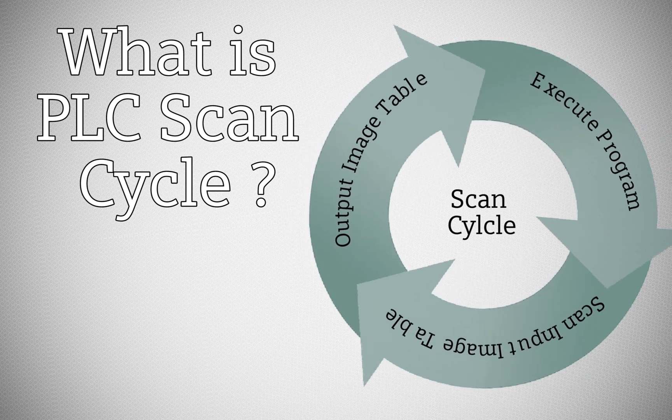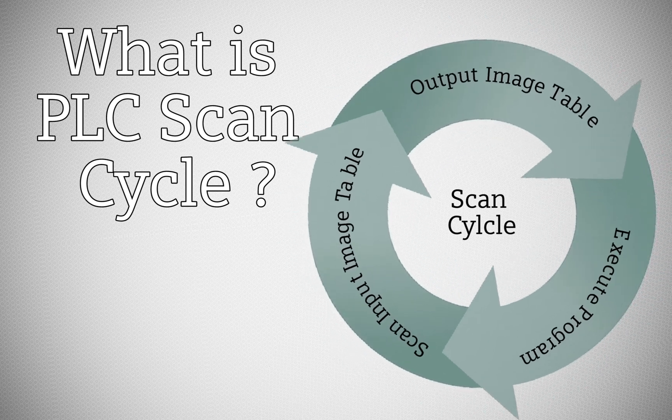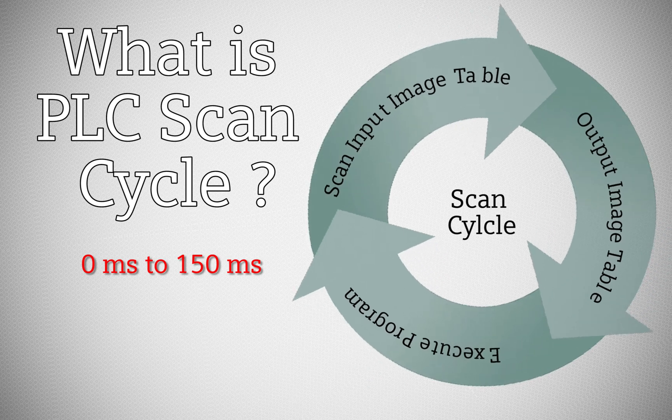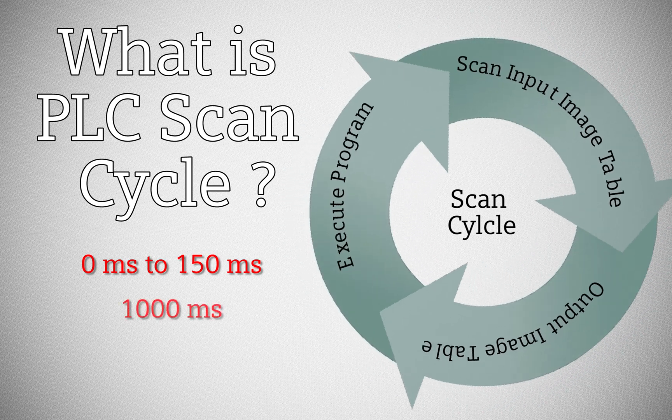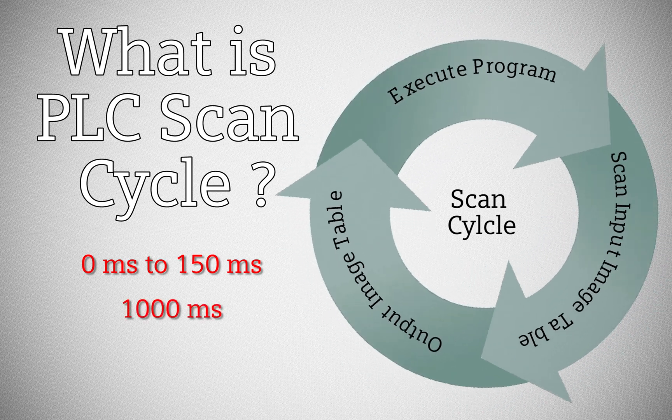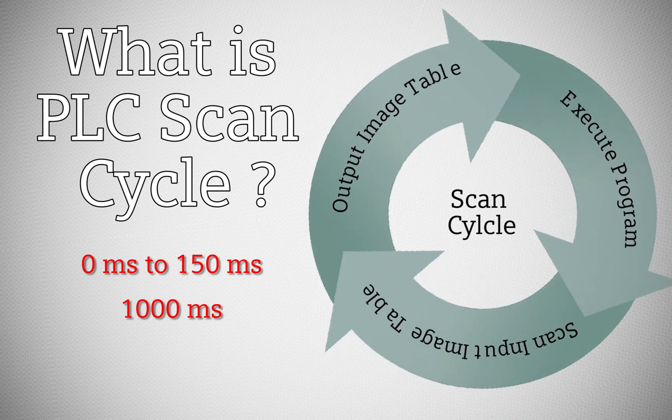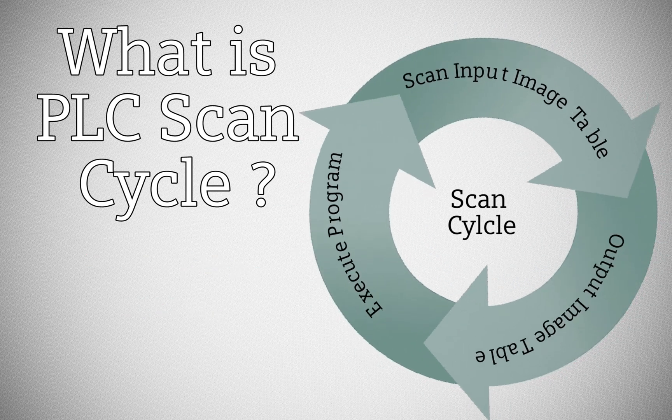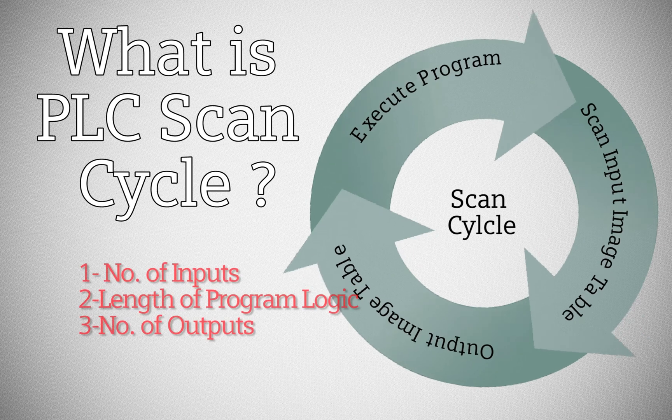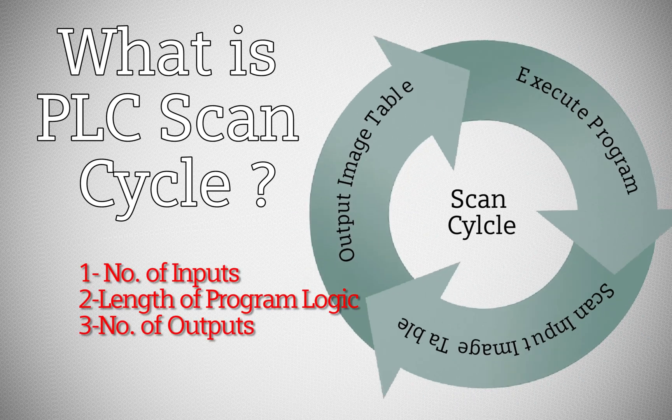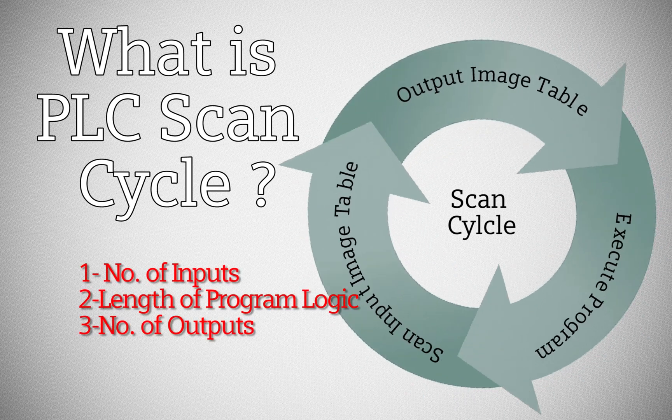The PLC scan time varies from 0 milliseconds to 150 milliseconds and can be as large as 1000 milliseconds. The variation in the scan time depends on the following factors: number of inputs, length of the logic, and number of outputs.